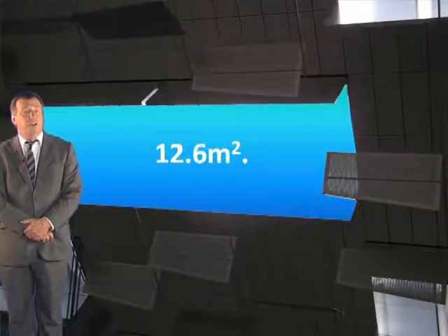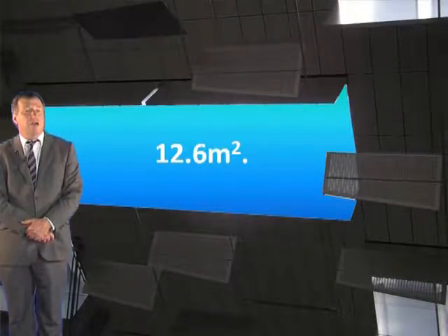In the last step, step 6, we calculated required ventilation areas and mechanical extraction rates, and now let's suppose, for example, that we need 12.6 square metres of aerodynamic free ventilation per reservoir. Let's look at how this can be provided. It cannot be provided as a single ventilator, as ventilators don't generally get made that large.